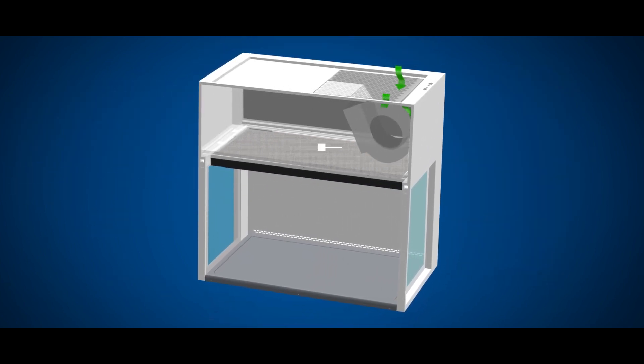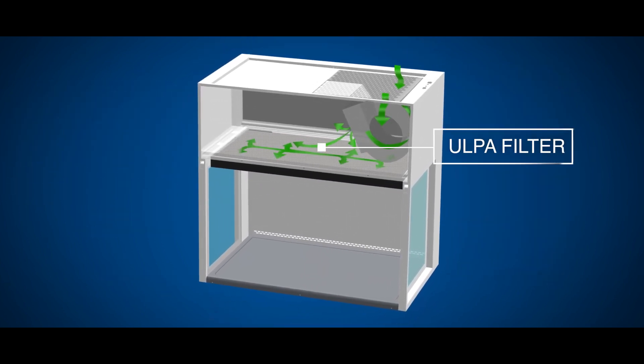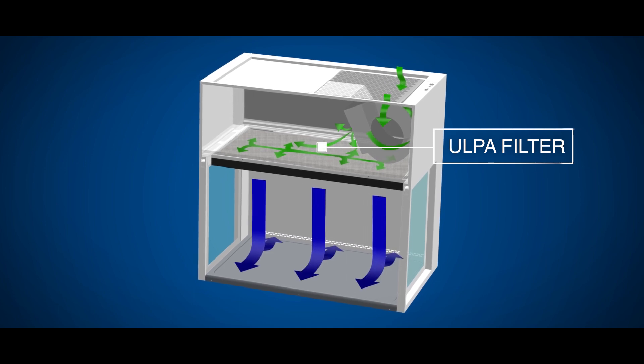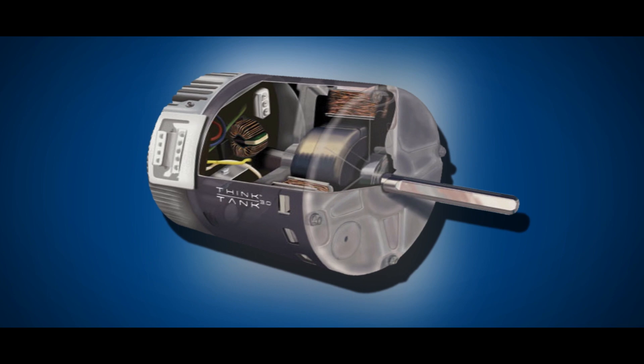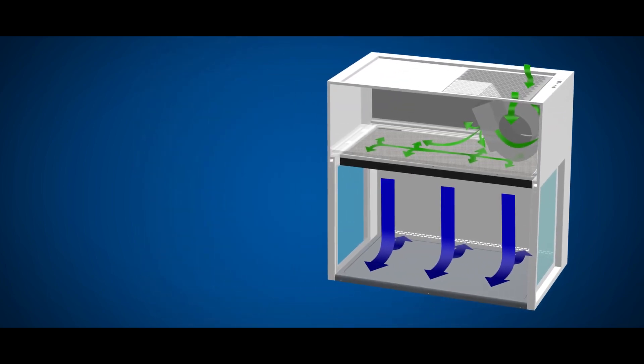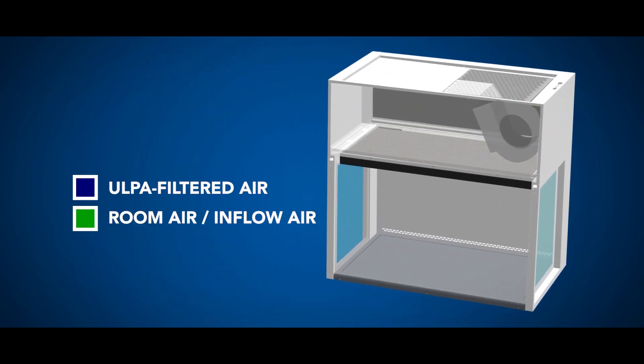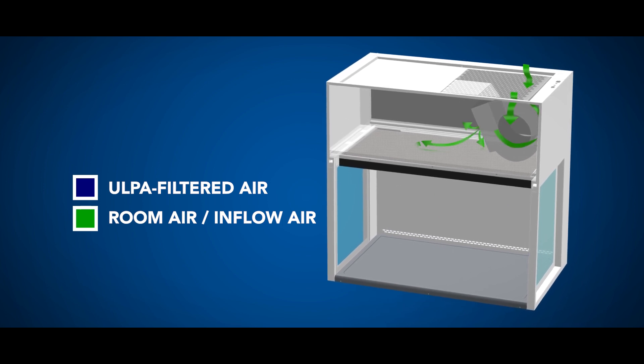Air is drawn from the top of the cabinet and passes through the pre-filter. The DC ECM blower facilitates air movement towards the ULPA filter to produce a stream of clean laminar air within the work zone, diluting and flushing contaminants present in the interior.